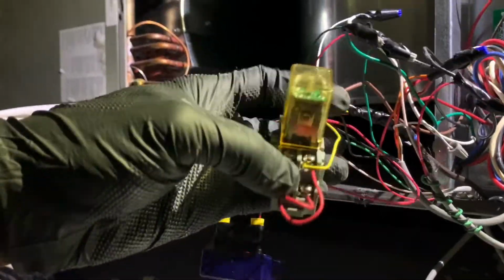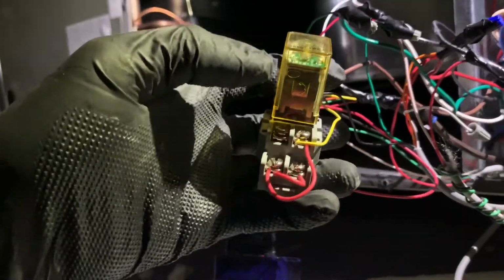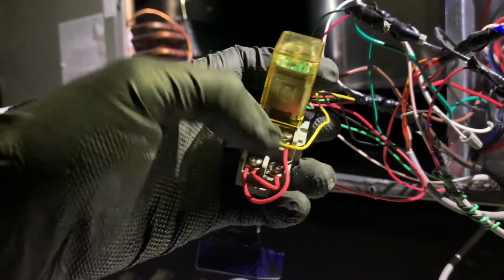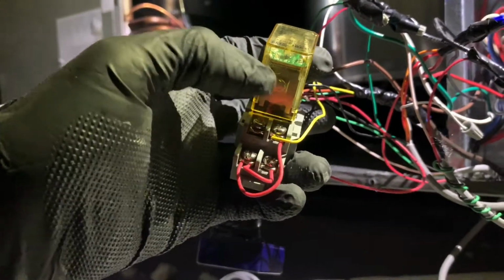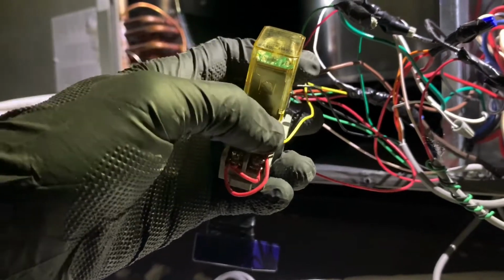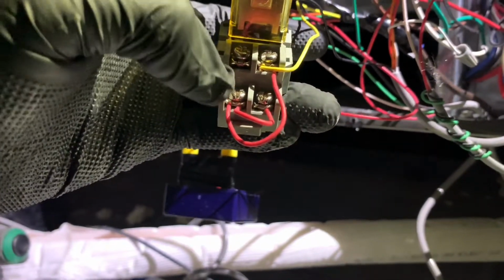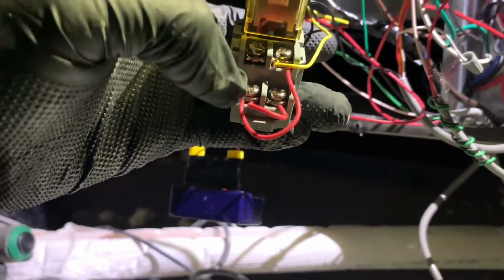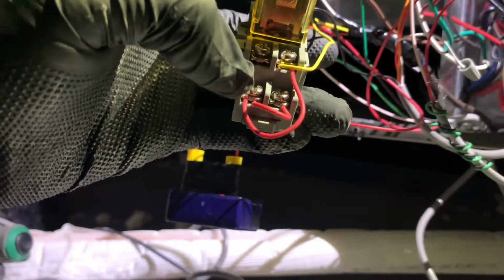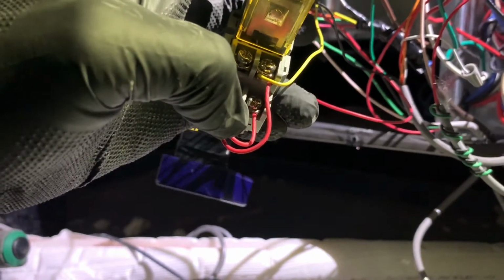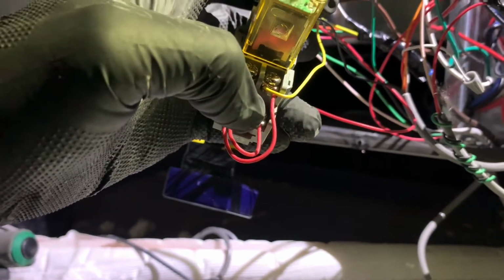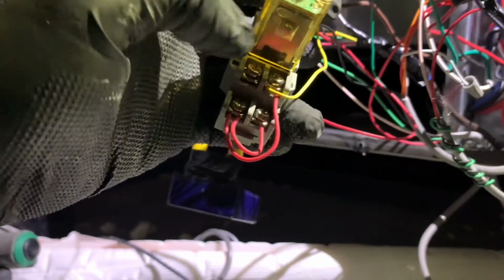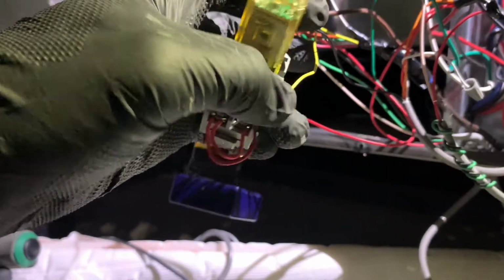And so I'll land it on one side of the coil of this relay, right? It's going to activate this relay, the cooling signal from the thermostat. Once that happens, you can see the same 24 volts came down to the bottom of one side of the normally open contact of the relay, and it's also shunted over to the other side of the normally open contact of this relay, or contacts. So this same wire comes here, and it goes here, same cooling signal.